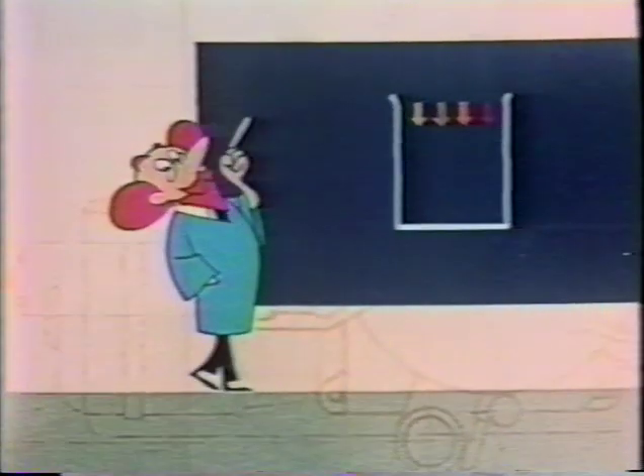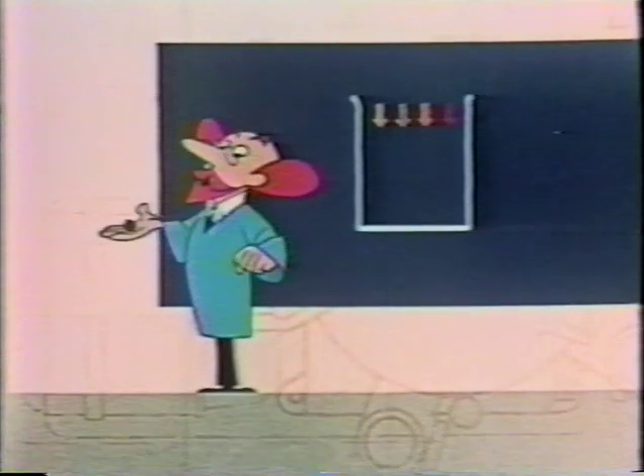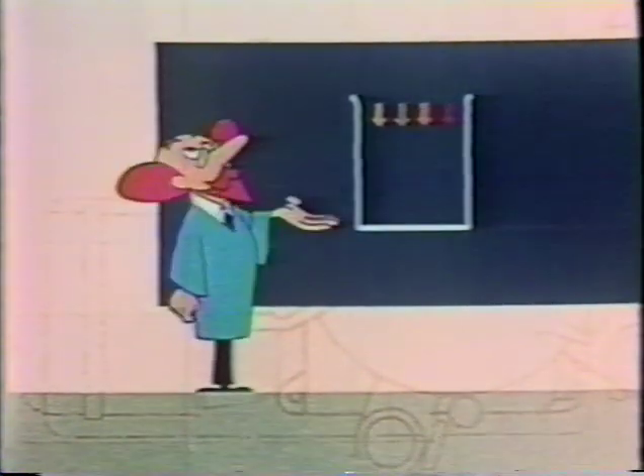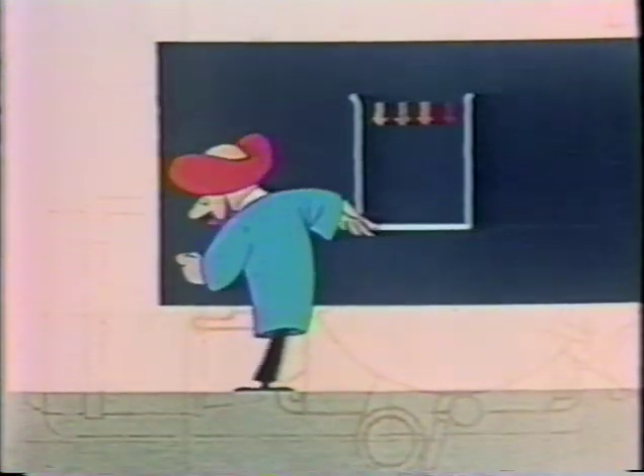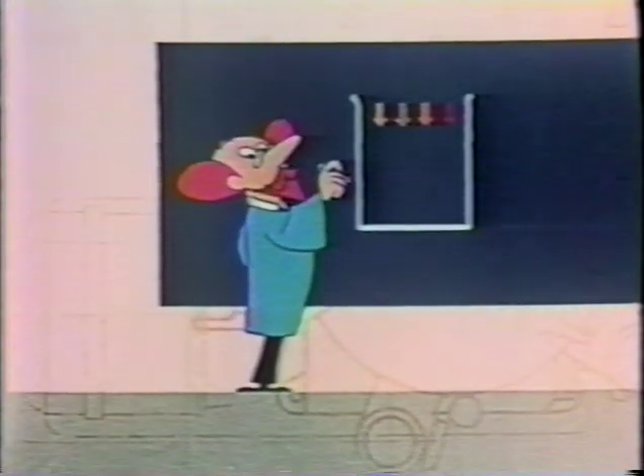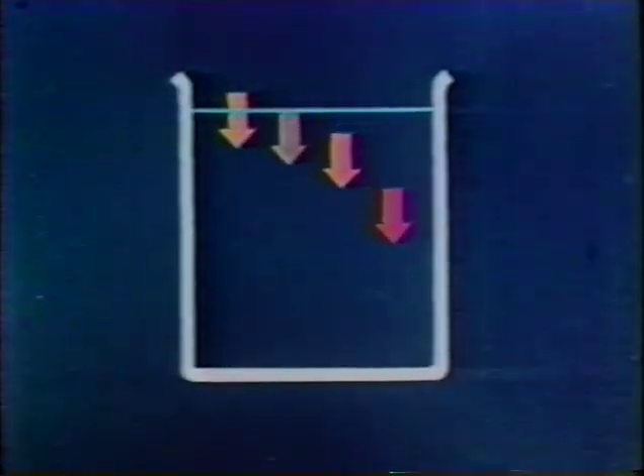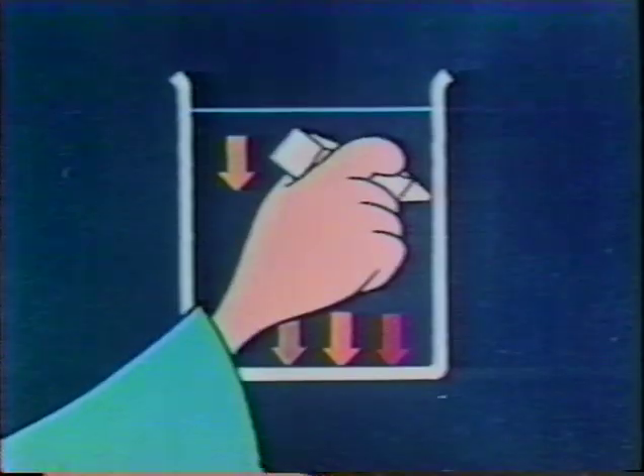Let's examine things carefully for a moment. In gravity separation, there are two major factors: one is time, the other is gravity. The time required to complete this settling process depends in turn upon two factors. Firstly, the settling speed of the particles. Secondly, the distance these particles have to travel before they actually settle. It is by reducing this distance that the separation process can be speeded up. Very simple.